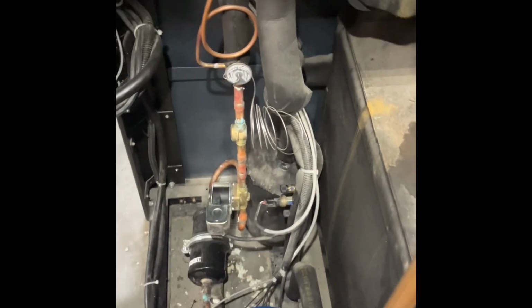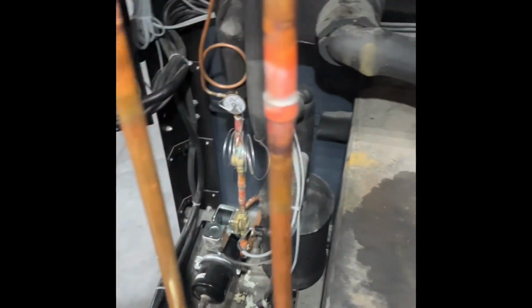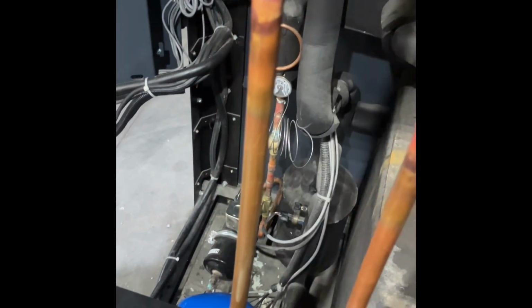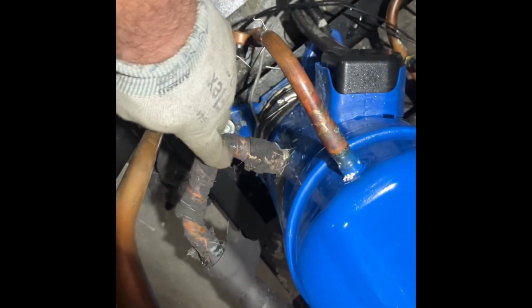But I am kind of expecting that as soon as I put nitrogen to this refrigeration system, this guy's going to wave at me. I may be wrong — a refrigerant leak doesn't always have to be oily, or I may find a leak somewhere I'm not even expecting. But so far everything seems pretty clean, except for the low pressure side of this.